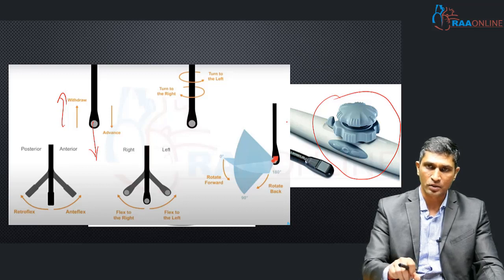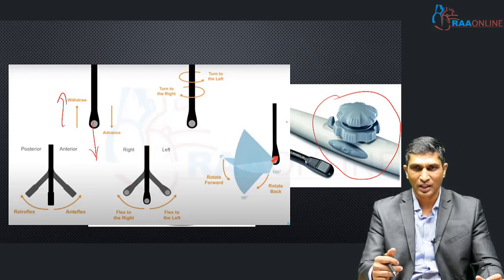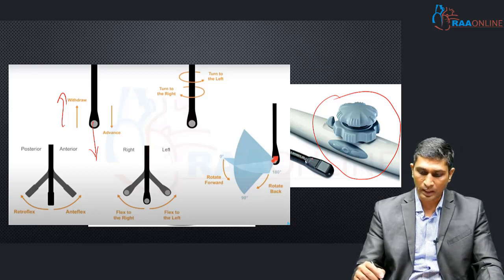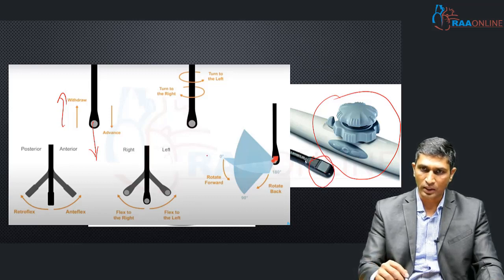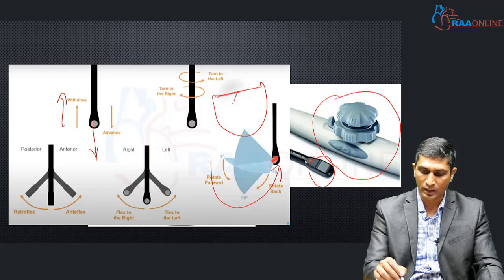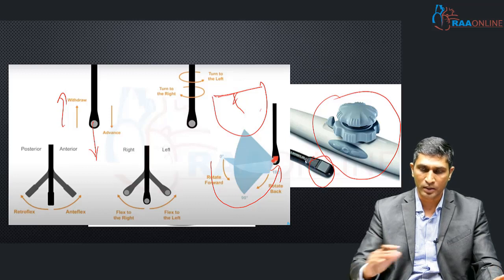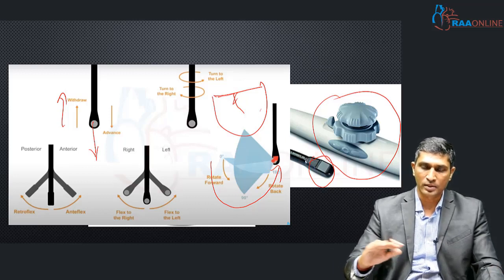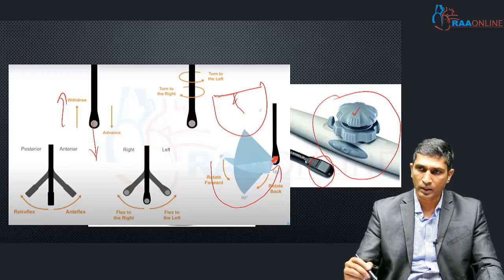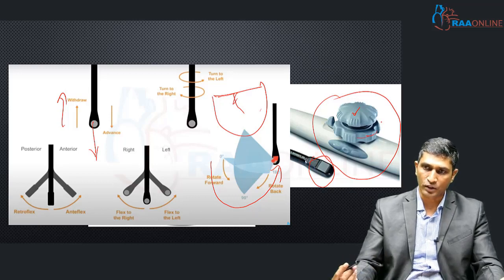Rotating to the right visualizes the right side structures, rotating to the left visualizes the left side structures of the heart. The probe has a multiplanar axis which rotates from 0 degrees to 180 degrees, dissecting the heart in various sections. There are two knobs: one used to rotate left and right, and the bigger knob used for anteflexion and retroflexion.